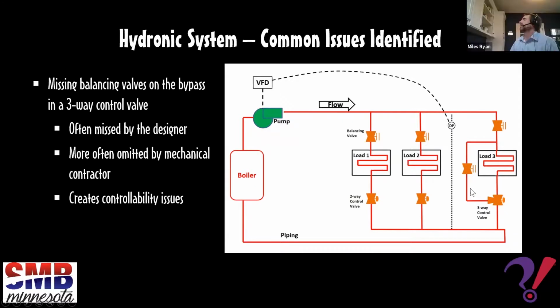Oh, did I say it backwards? I'm not sure, but basically you're measuring this one for flow. So if you have a design flow of, let's just say, 100 GPM to make it easy, and you got 100 GPM here, but the minimum flow for your primary piece of equipment is 50, then you would put all these valves closed, this control valve to full bypass, and you would set that to 60, give yourself a little cushion. Right. So I might have misspoke the first time.